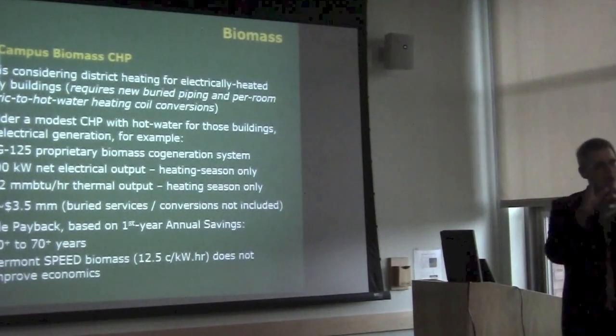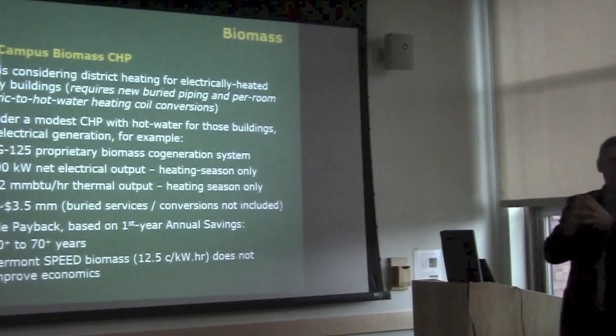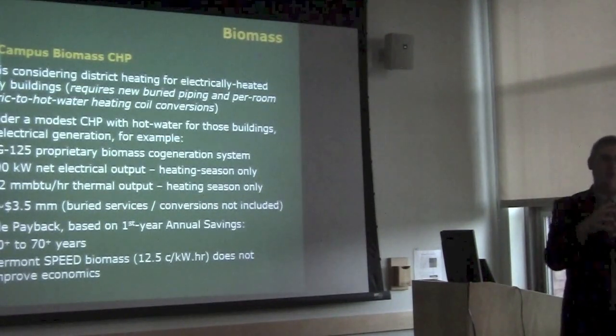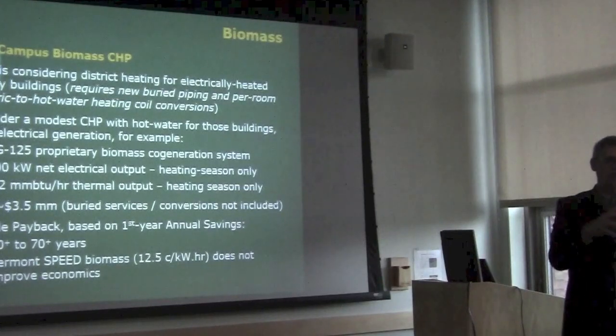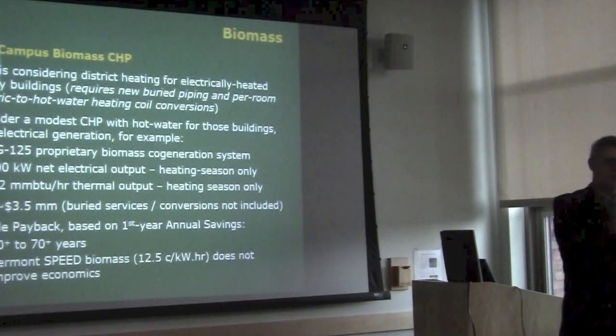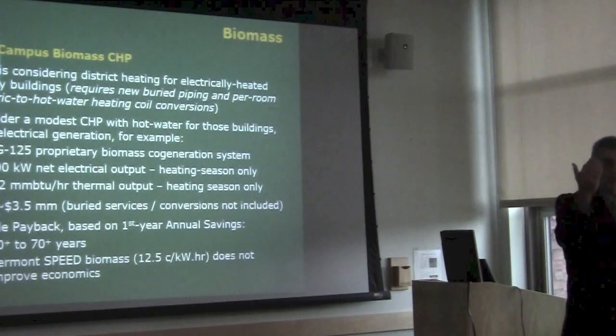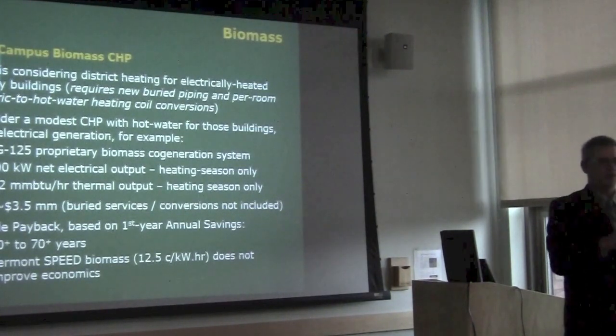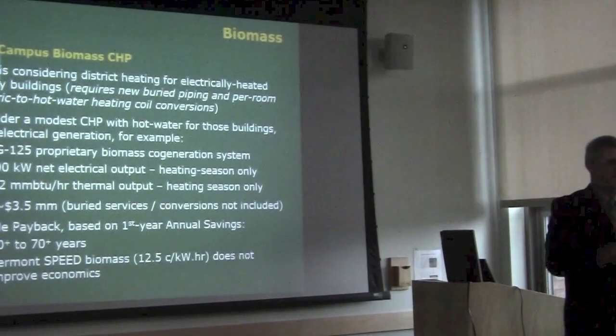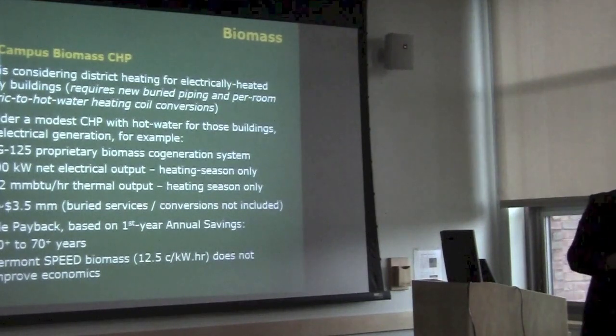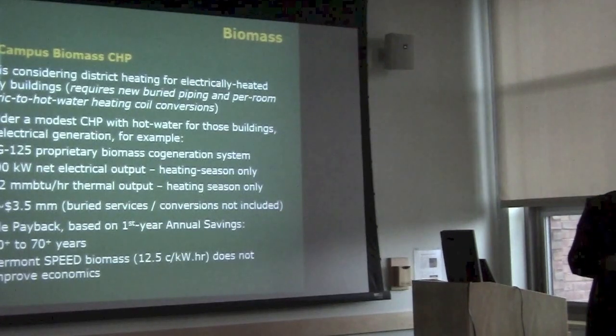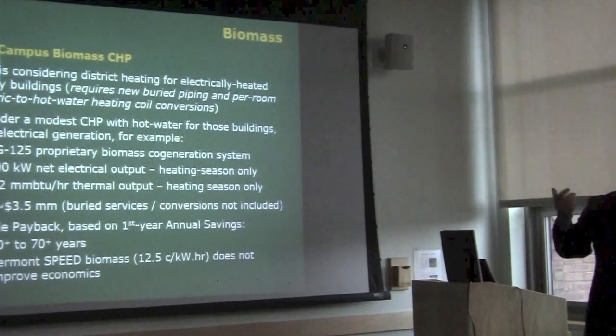It's such a small island of electricity. When you're looking at small kilowatts like this, the economy of scale really starts killing you. Cogeneration makes sense when you're talking like even the 3.5 megawatt at Cage, which is relatively small. Cornell has a 30 megawatt cogen, things like that. So you don't have the thermal load year round, and you also don't have an electric load at nighttime, so the ideal place is when you have a constant thermal load or a constant electric load, so you just let that unit hum away. Turn it on, run it to 100% and leave it there. Even the Cage struggles with that.